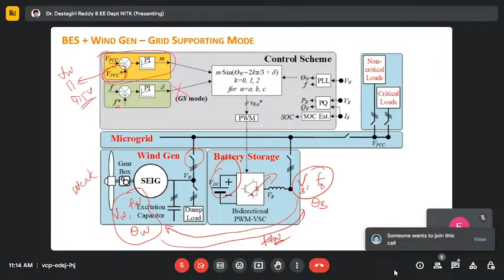Okay, so that's how it changes. So now what will happen? If there is a change in wind after synchronization, whenever wind velocity changes, it will get reflected in either voltage or frequency - in voltage and frequency - and that will get reflected finally in the P and Q coming from the wind turbine. It will get reflected in terms of P and Q, and it cannot influence the voltage and frequency, which is maintained by the voltage source converter.